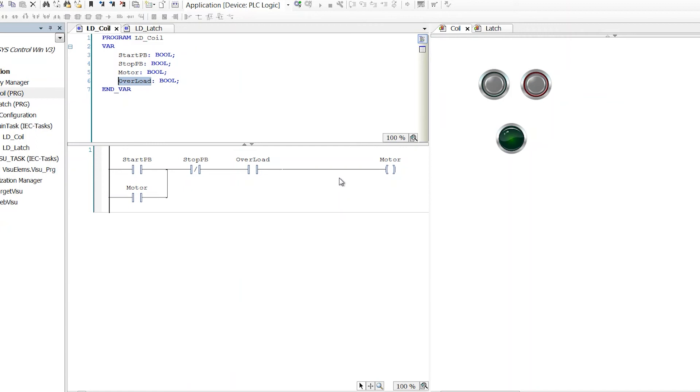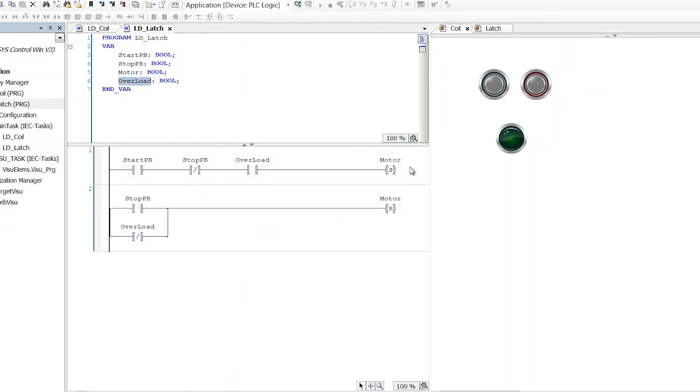Now, something you really don't want to do almost ever. I think I found one case where I broke this rule in my life as a controls engineer. Don't ever write to something with a regular coil and also a set or reset coil. That makes it really confusing for the next guy. Yes, you can make a functional program.